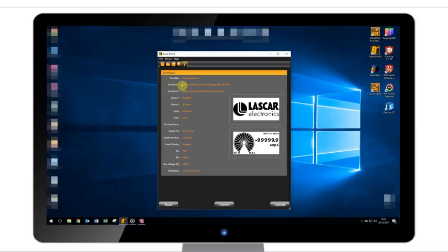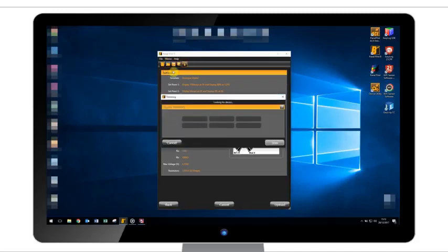The last feature to highlight is the trimming function. If your panel meter is supposed to display 100% at 5 volts, but instead is showing 98.5%, then plug in your meter, click Device, and then Trimming. This will give you the option to enter your expected and actual display points, and the device will then be calibrated to amend these errors.